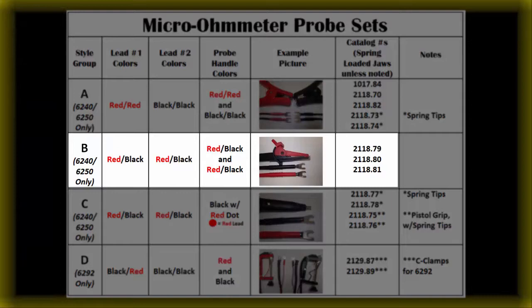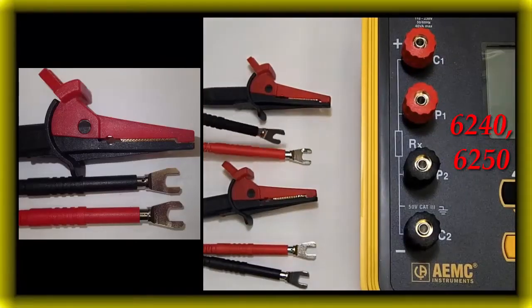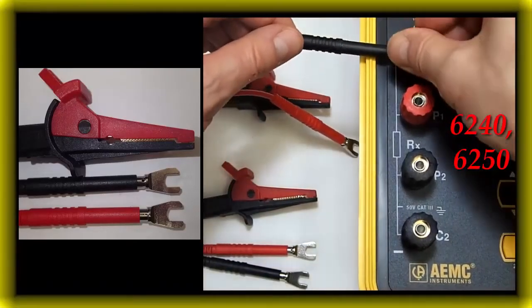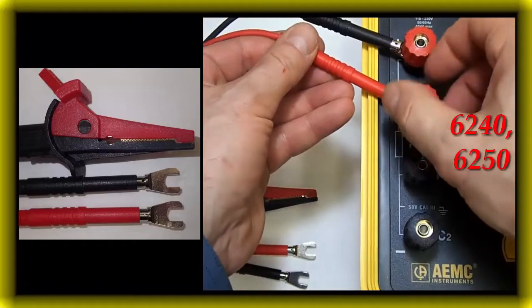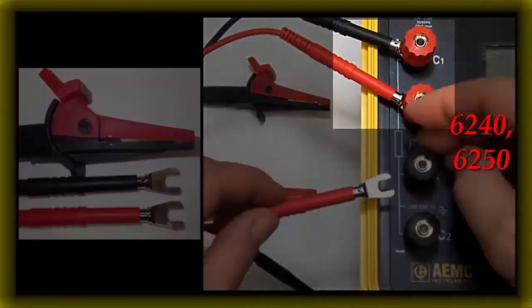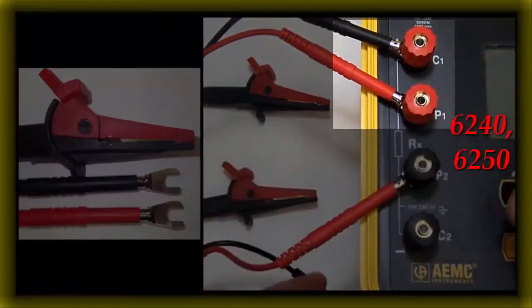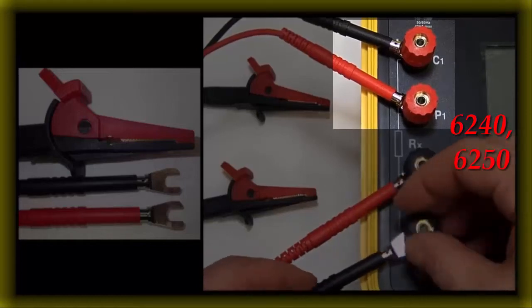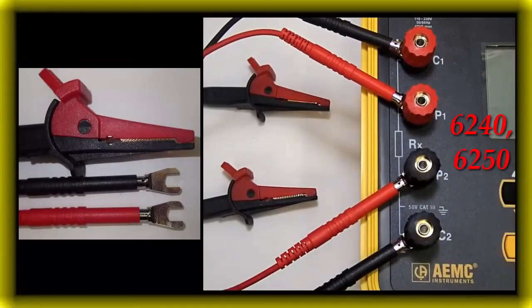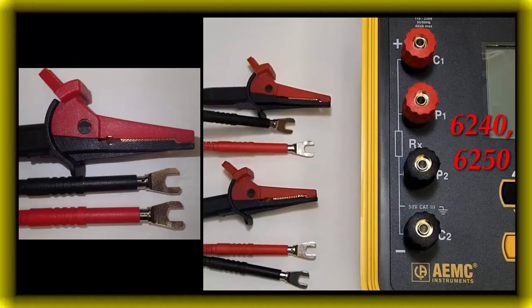Style Group B for 6240 and 6250. When using the 3 part numbers from Style Group B, where the leads are red, black, and red, black, then the connections will not match the color coding on the instrument's terminals. In these cases, the black lead will always connect to a C terminal and the red lead will always connect to a P terminal, or vice versa. Note, these leads are not approved for use with the model 6292.